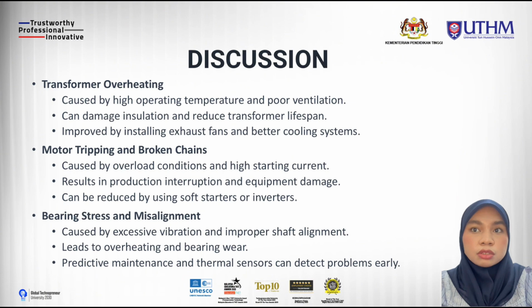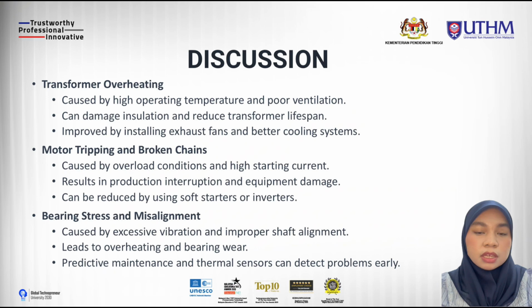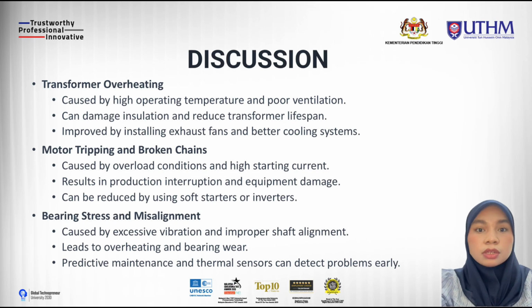One common issue is transformer overheating, which is caused by high operating temperature and poor ventilation. This can damage the insulation and shorten the transformer lifespan. To overcome this problem, an exhaust fan and improved cooling system can be installed.